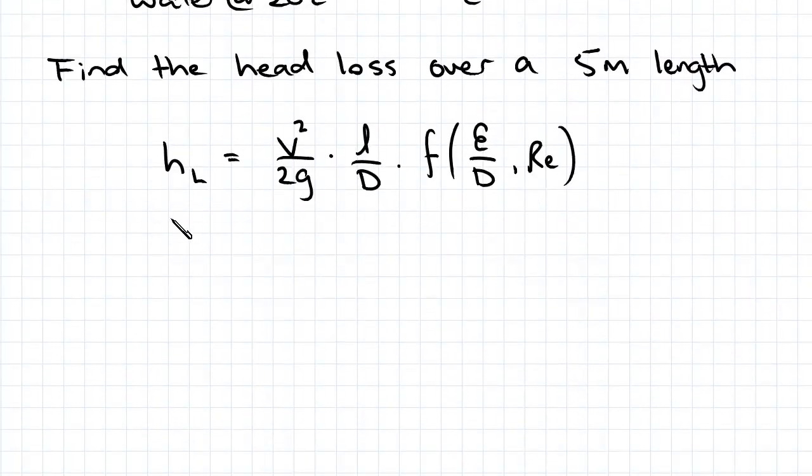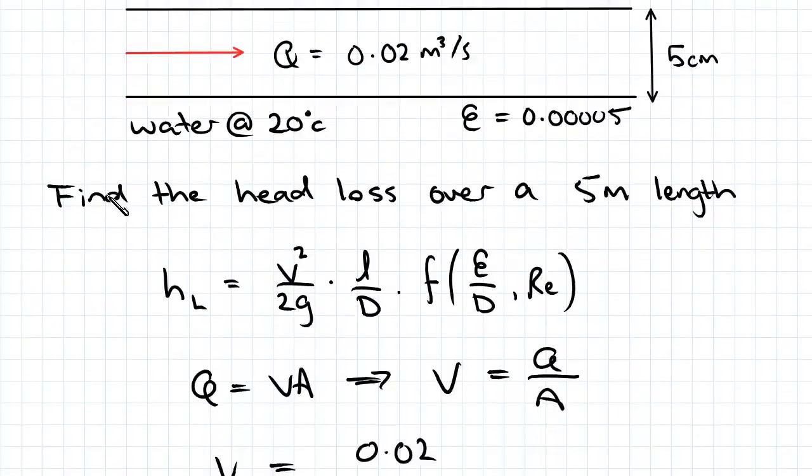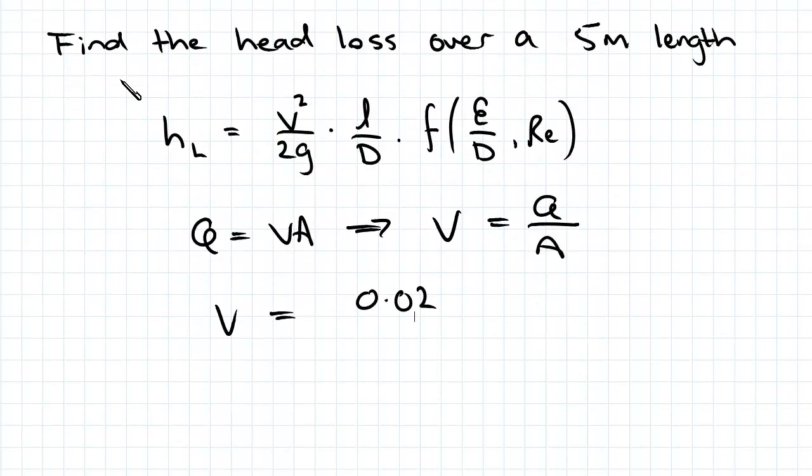Subbing in our values for that, we've given 0.02 meters cubed per second, and we're dividing that by pi d squared on 4. D was 0.05 squared times pi on 4, and that simplifies down to 10.19 meters per second.